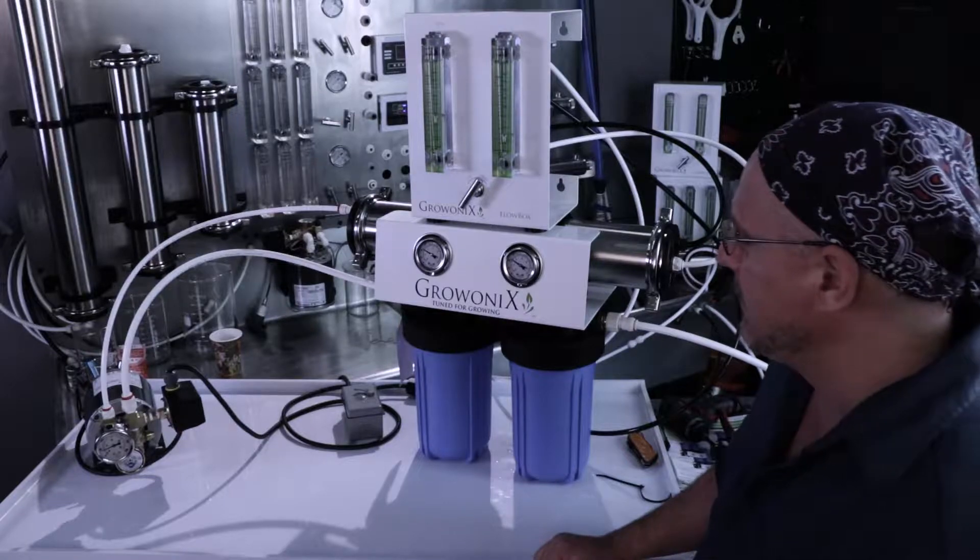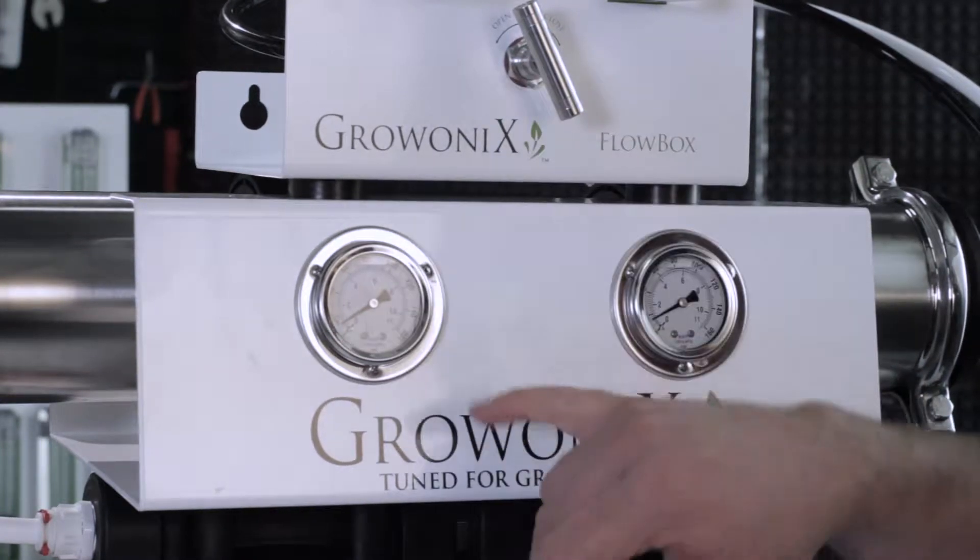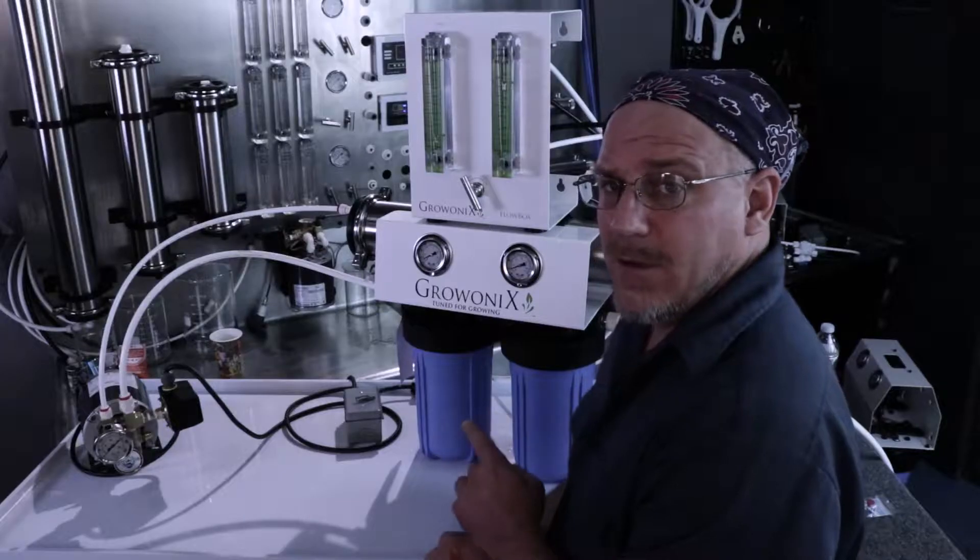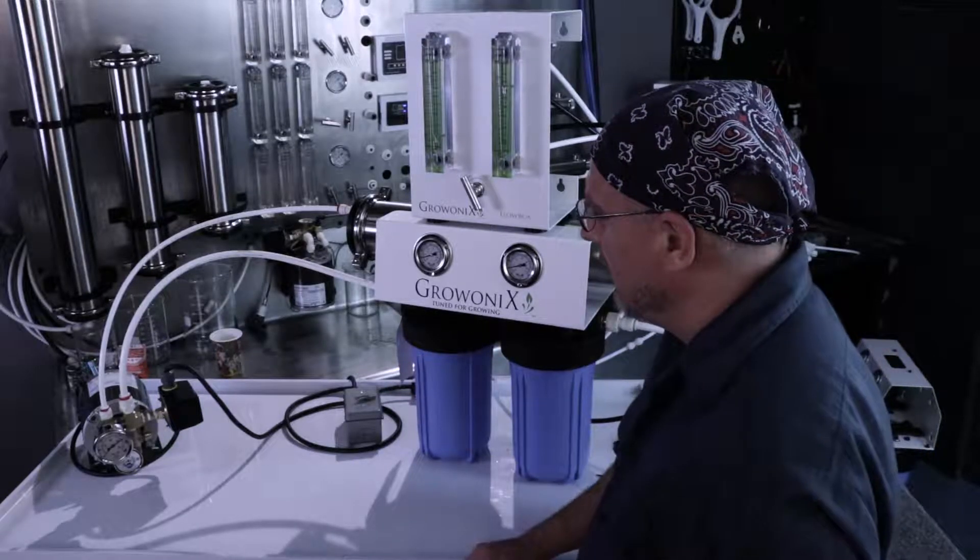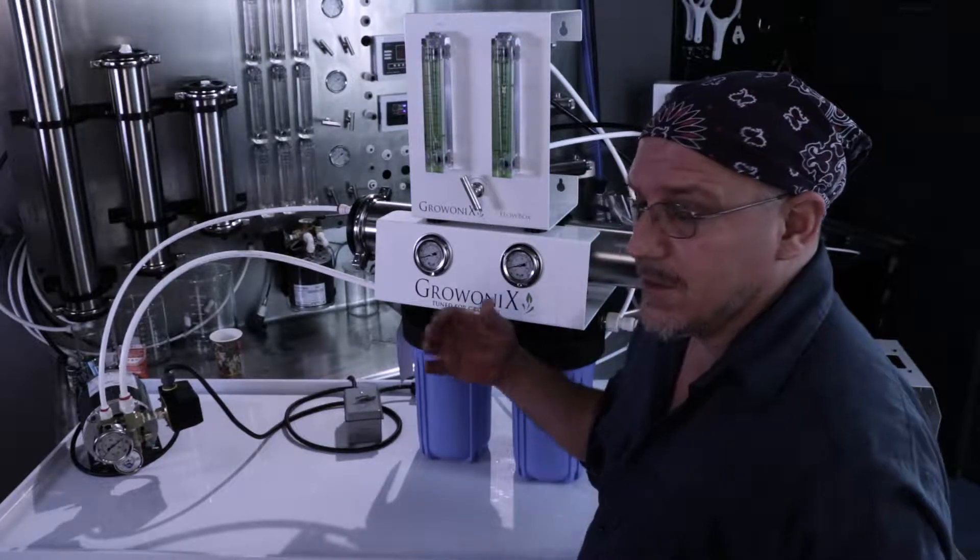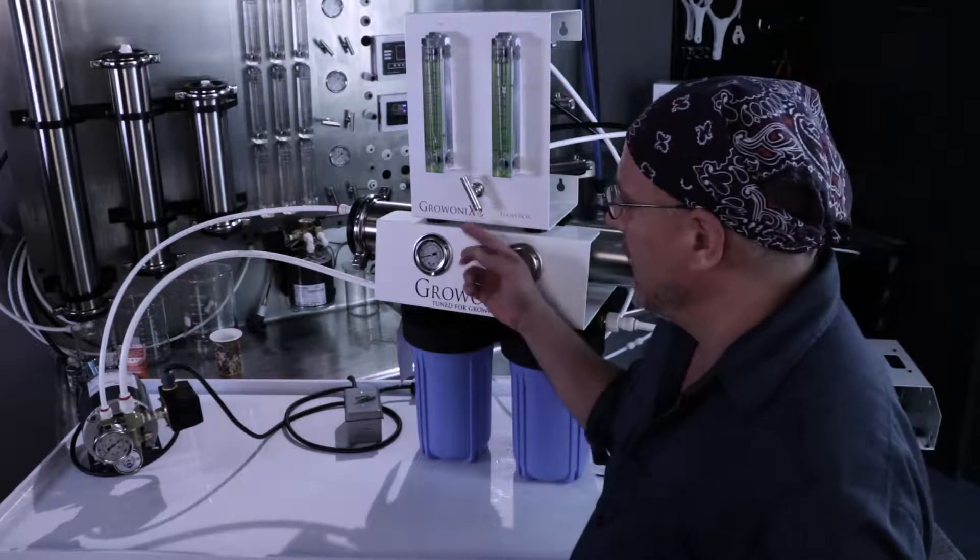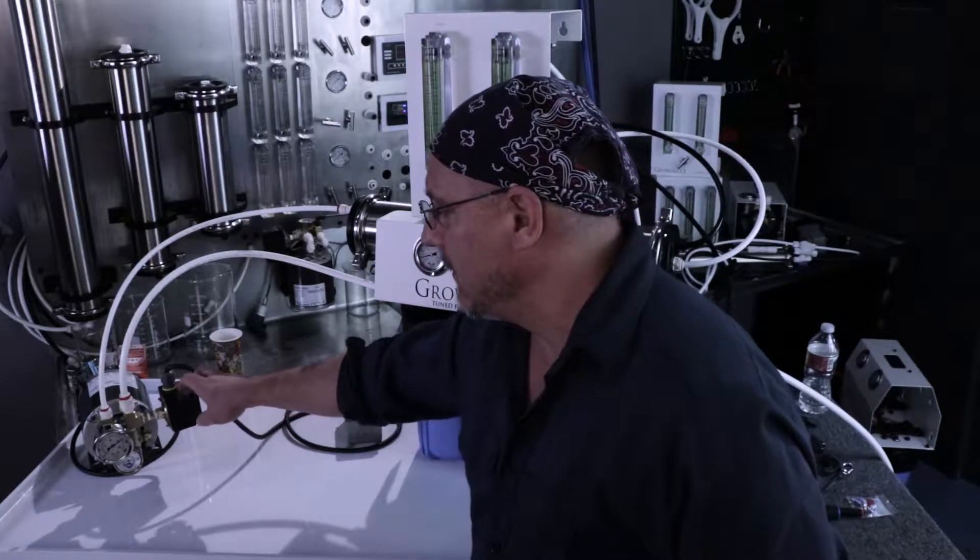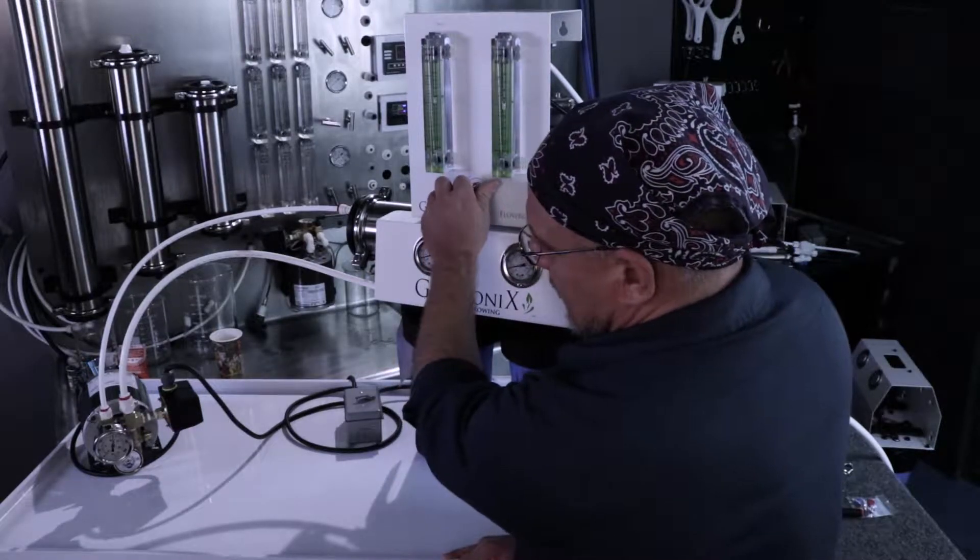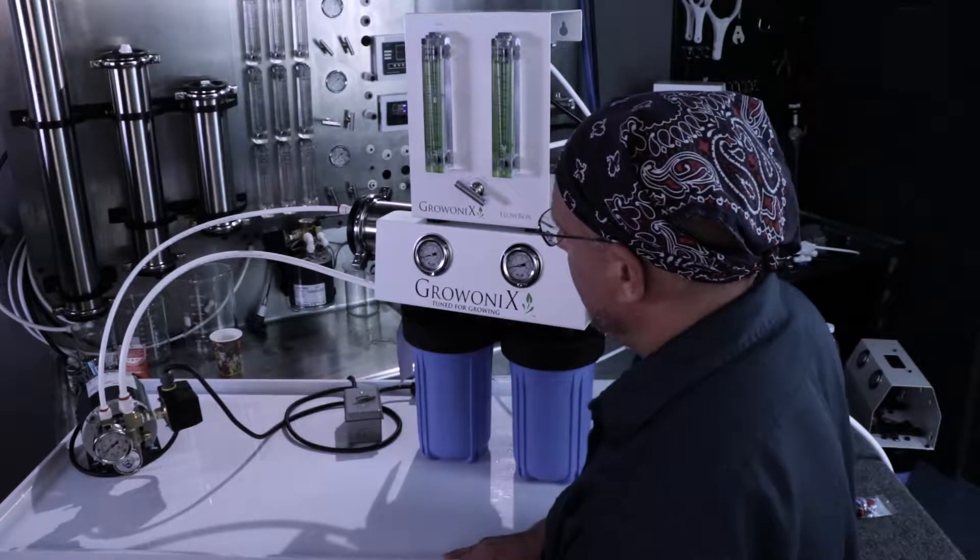Let's turn it on. This RO has a low pressure feed water condition. I've artificially manipulated it and I'm running at about 18 psi, which is getting really close to the cutoff point, which is around 10 psi. What happens is if somebody turns the sink on, flushes a toilet, or I go to flush this machine, I could lose my headroom and the pump is going to cut off because it has a low pressure cutoff switch. There, my pressure goes down and jumps up. Now my pump is cycling.